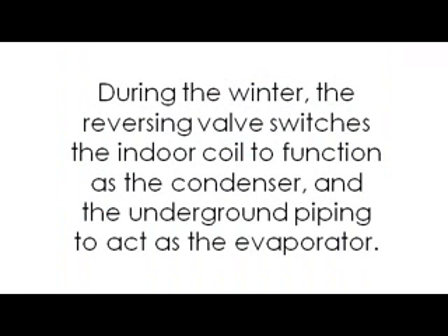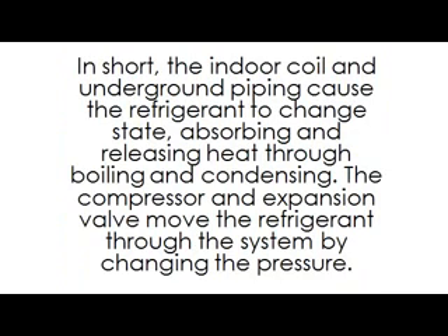During the winter, the reversing valve switches the indoor coil to function as the condenser, and the underground piping to act as the evaporator. In short, the indoor coil and underground piping cause the refrigerant to change state, absorbing and releasing heat through boiling and condensing. The compressor and expansion valve move the refrigerant through the system by changing the pressure.